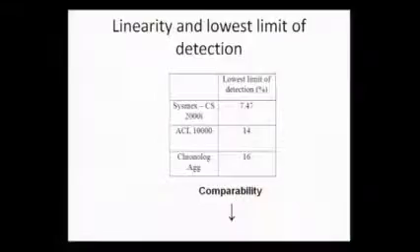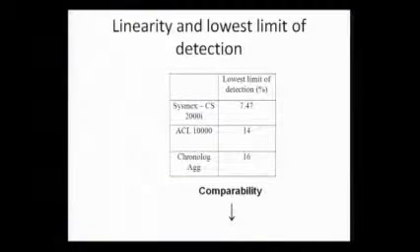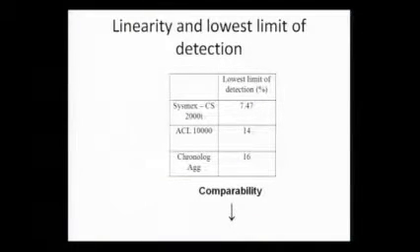The advantage of the Sysmex CS2000i is that the lowest limit of detection is 7.47, compared to ACL 10,000 which is 14, and Chronolog which is 16.